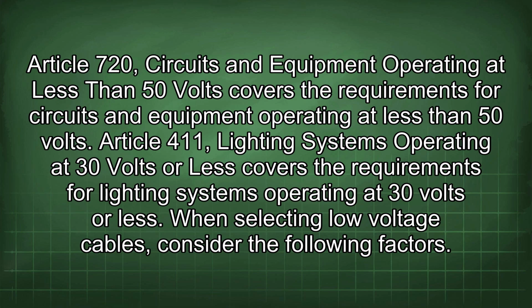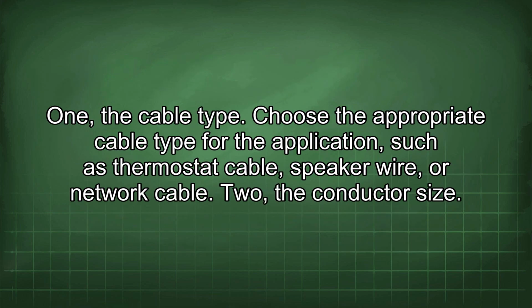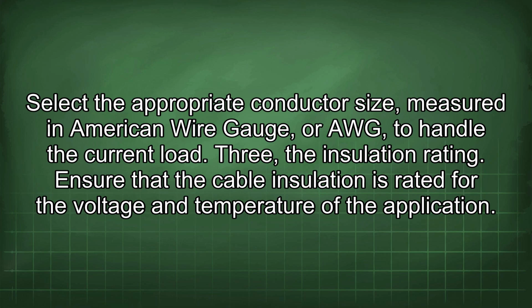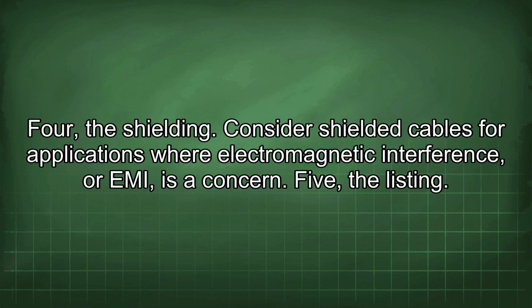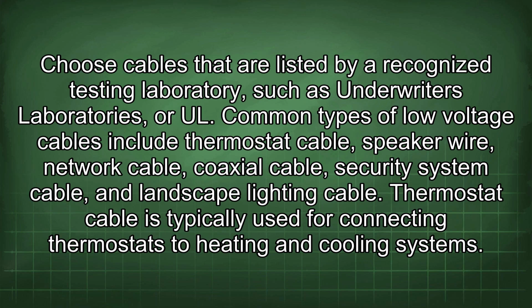When selecting low voltage cables, consider the following factors. First, the cable type: choose the appropriate cable type for the application, such as thermostat cable, speaker wire, or network cable. Second, the conductor size: select the appropriate size, measured in American Wire Gauge, or AWG, to handle the current load. Third, the insulation rating: ensure that the cable insulation is rated for the voltage and temperature of the application. Fourth, the shielding: consider shielded cables where electromagnetic interference, or EMI, is a concern. Fifth, the listing: choose cables that are listed by a recognized testing laboratory, such as Underwriters Laboratories, or UL.